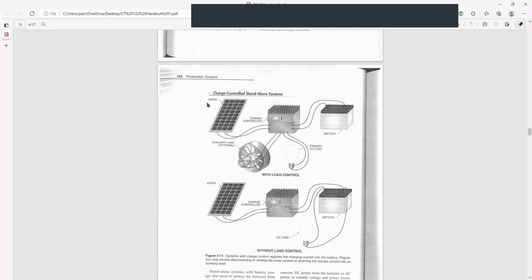Yes. So sometimes you can do it like the bus stops that have lights, have solar panels on them, if they have a little roof, they work like this. There's an array, a small array on top. It has to store in the battery because the lights work all night long, in those bus things. And so it goes through a charge controller and is stored in a battery. So they don't need an inverter. They have a DC load, DC light.